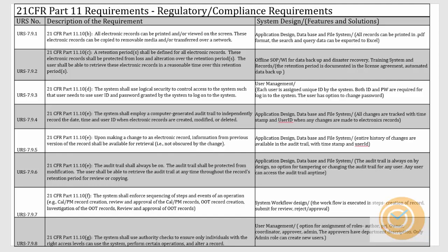A retention period shall be defined for all electronic records. The objective here is that you should be able to retrieve the documents. First thing, you have to define how long your backup should be kept and how long your data should be retained. And in case you have a disaster or some failure, you should have an SOP to show how you can recover the data if the system fails.